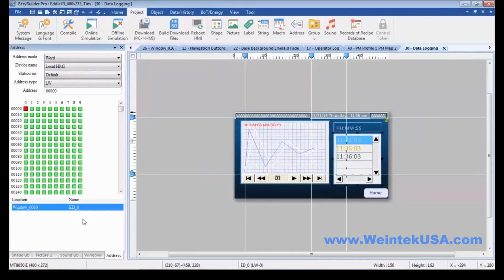Let's say that you were talking about macros. A macro might execute every time they hit a button, but it may do something based off of a value that you store. So I would store those values in retentive registers and then pull those values out of the macro to go with whatever the new data was when they hit the button. So this helps you locate those.